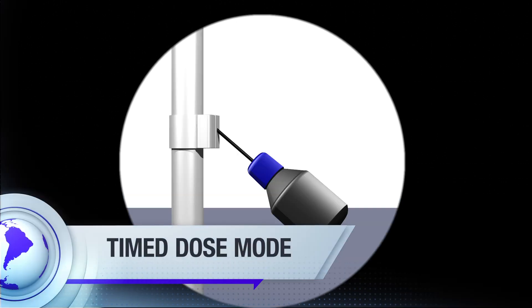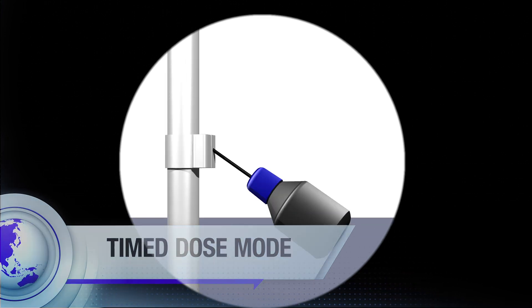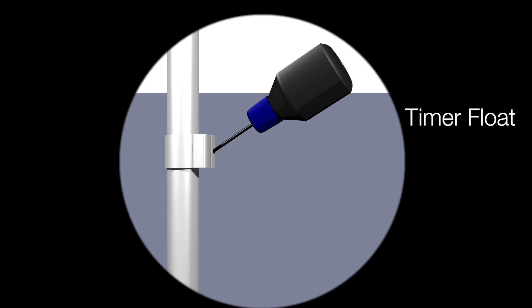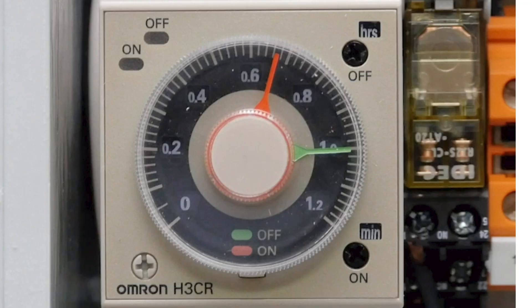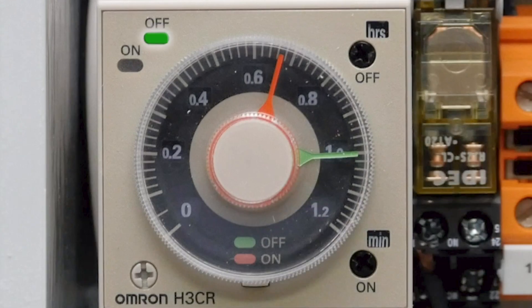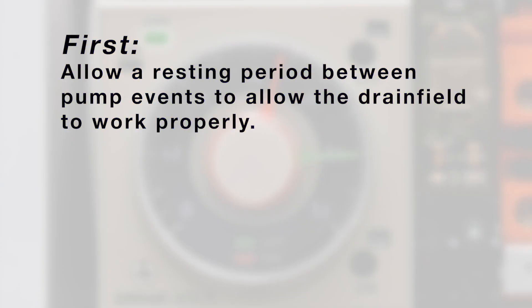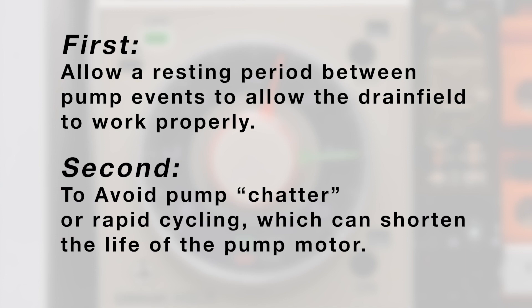In time dose mode, the pump on/off float is replaced with a timer on/off float. When the liquid level in the tank raises the timer float to the up position, it will energize the timer rather than the pump and begin the timer off cycle. This happens for two reasons: first, we want to allow a resting period between pump events to allow the drain field to work properly, and second, we want to avoid pump chatter or rapid cycling which can shorten the life of the pump motor.